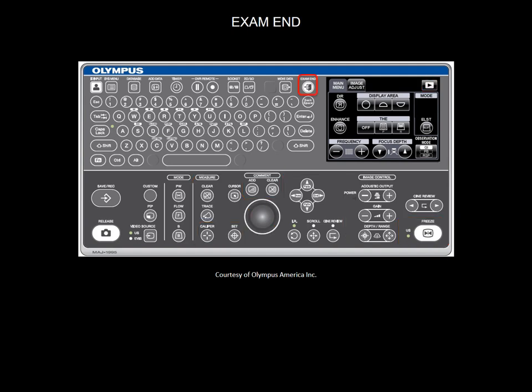If you are performing back-to-back cases and you don't turn off the machine, you will be using the previous adjustment values. Exam End button allows you to go back to the default original setting.